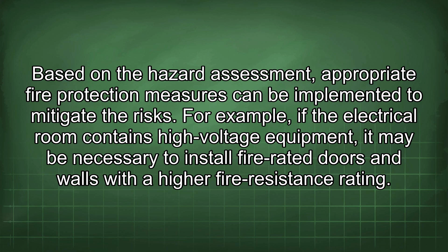Furthermore, it is essential to consider the potential for fire to spread from the electrical room to other parts of the building. This assessment should take into account factors such as the construction of the walls and floor surrounding the electrical room, the presence of any openings or penetrations, and the proximity to other critical areas. If there is a significant risk of fire spreading, additional fire protection measures may be necessary, such as fire stopping or fire-rated sealants. In addition to the physical fire protection measures, it is also important to implement administrative controls to prevent fires in electrical rooms.